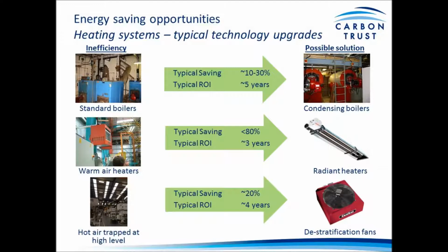These use large heat exchangers to extract as much heat as possible from the waste flue gases. Typical saving, as stated, is 10 to 30%, and typical return on investment, because it's relatively high capital expenditure, you're looking at around 5 years as a ballpark.